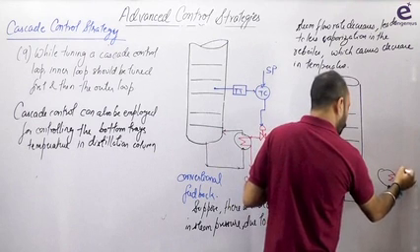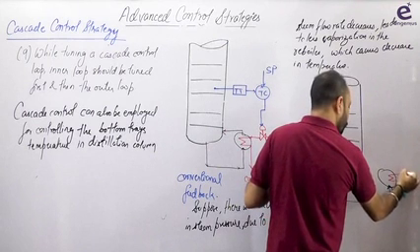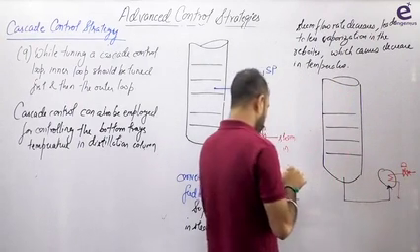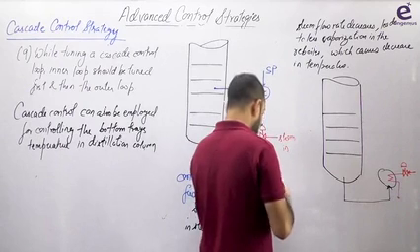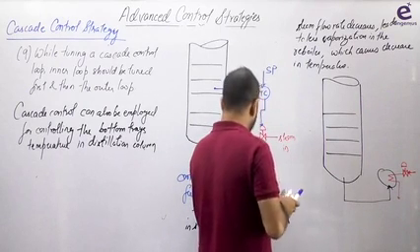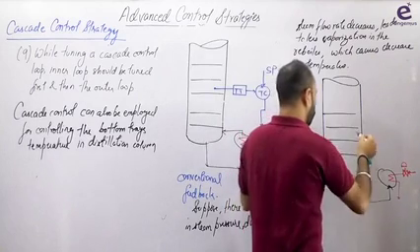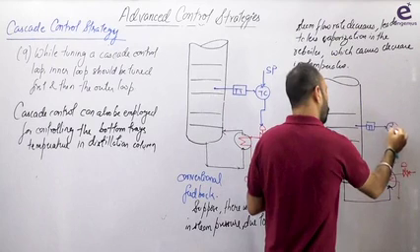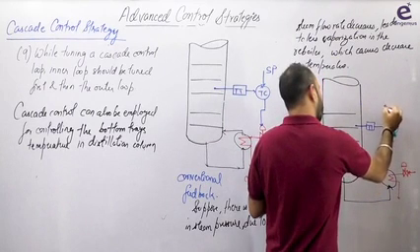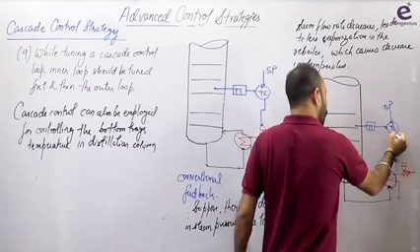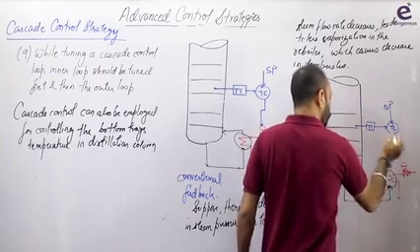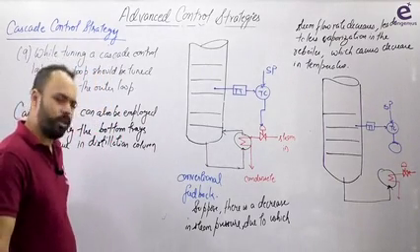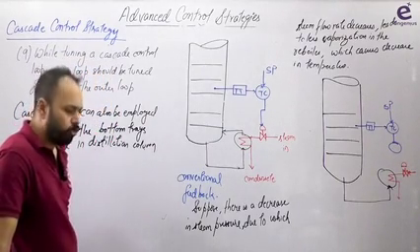I'm not writing all the things now. The steam is coming from the steam header. Now what I'm going to measure, I will install one more controller. This is the temperature measurement taking place as before, going to the temperature controller, and set point is provided. This temperature controller has hired one more controller, that will measure the steam का pressure. Suppose if pressure has decreased, due to which the flow has decreased, तो pressure measure करने की जरूरत नहीं है. This is the flow controller only, right?